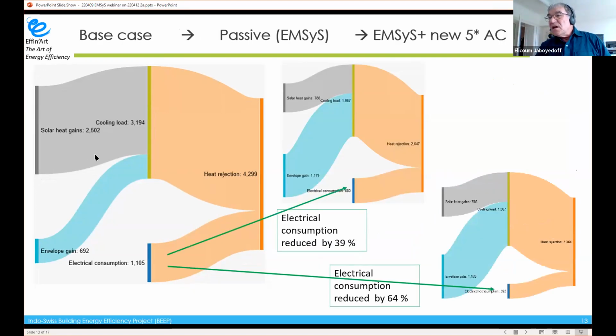Now if you take again the basic 1 star system, and go to a reduction of solar gain, having only an external movable shading but keeping the original 1 star, you see that you are already reducing from 1100 to less than 700. So you reduce electrical consumption, keeping the same AC, with the shading by almost 40%. Now, if you combine the two, adding the external movable shading and a new 5 star AC, you are reducing the total from 1100 down to less than 400, so about 64%.